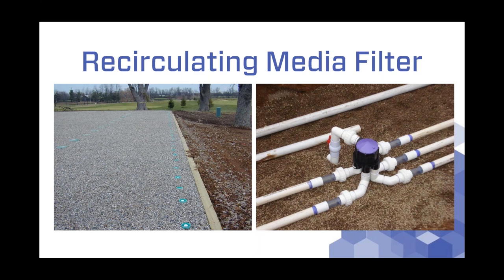For the zoning, we use a component called a multi-zone valve — the black fitting with the purple top. You can see the inlet coming in with a red-handle ball valve so you can turn it on or off for maintenance, with unions on all the outlet and inlet piping. There's clear piping on the outlets so we can see the flow for each zone. The way these work: a dose comes in, it doses zone one, and at the end of that dose an internal cam rotates so the next pump cycle flows to zone two, then zone three, zone four, and so on. Multi-zone valves are available with two, four, or five outlets.